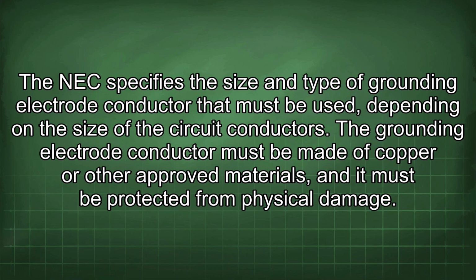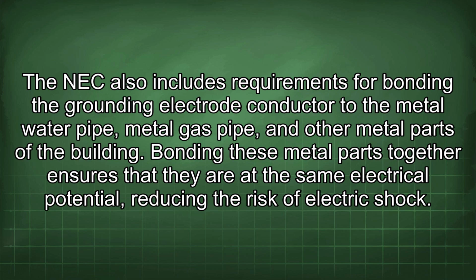The grounding electrode conductor must be made of copper or other approved materials, and it must be protected from physical damage. The NEC also includes requirements for bonding the grounding electrode conductor to the metal water pipe, metal gas pipe, and other metal parts of the building. Bonding these metal parts together ensures that they are at the same electrical potential, reducing the risk of electric shock.